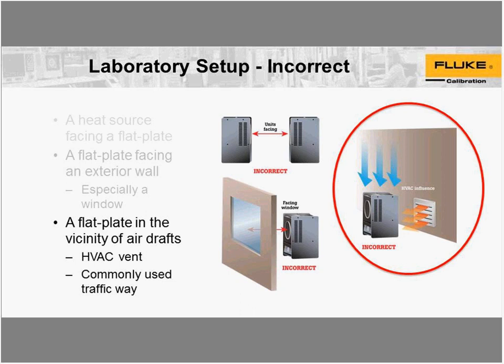You also don't want to have a flat plate in the vicinity of air drafts — for instance near an HVAC vent. That can really influence the amount of heat coming off the plate by convection and create an artificially lower temperature. Another thing to keep in mind: keep the flat plate away from commonly used traffic ways, such as a pathway next to the calibration area where people are constantly going by — especially a problem if you locate your instrument close to a door that's constantly being opened and closed. Again, the problem here is artificially high convection caused by air drafts in the laboratory.